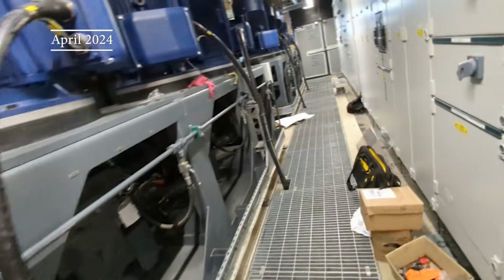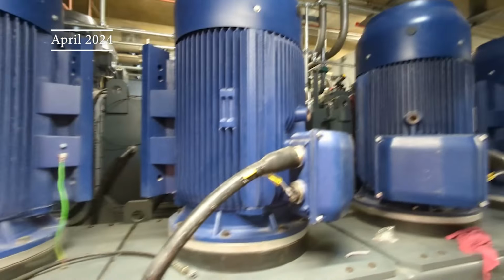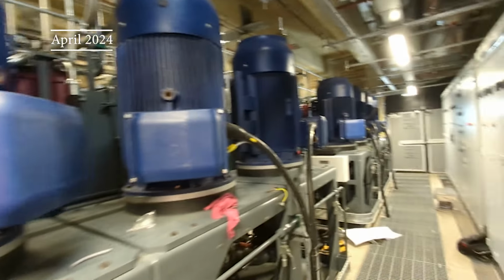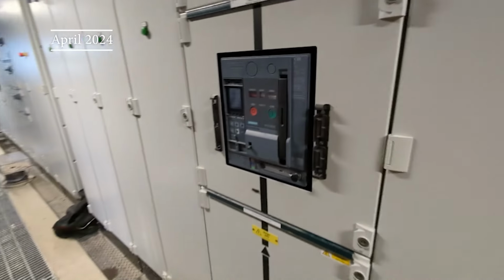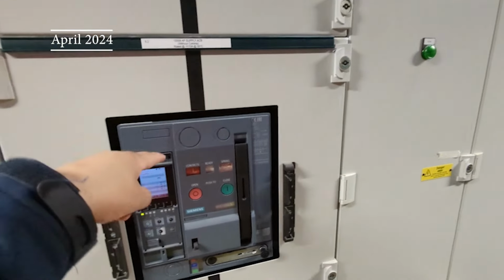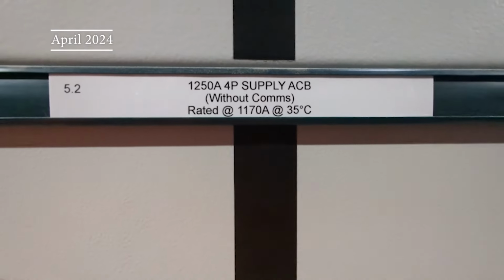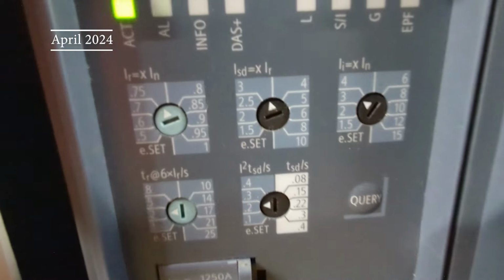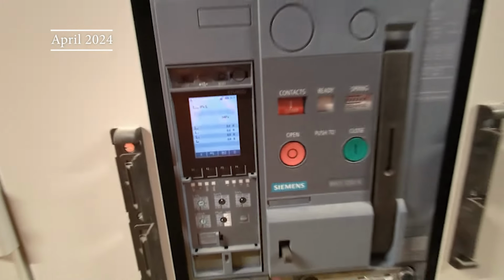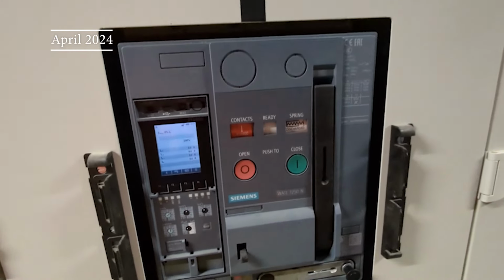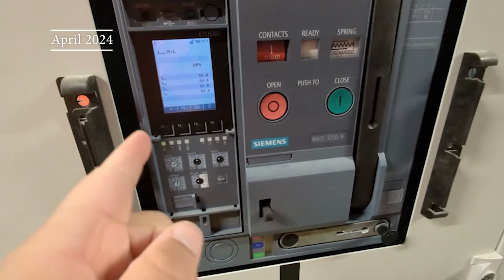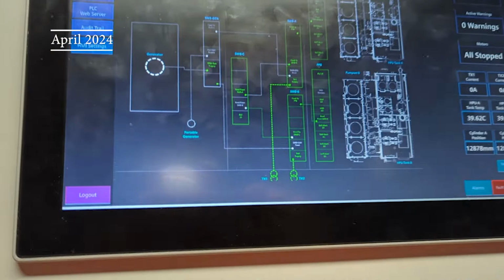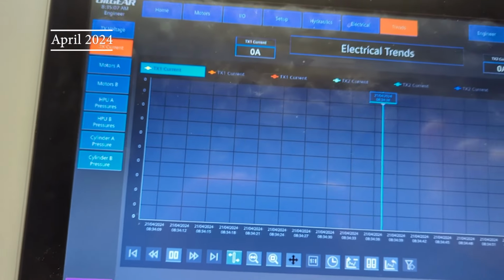Then if I take it next door to the hydraulics, these are the HPUs, the hydraulic motors and pumps that lift the bridge. So from inside the LV room into here, these get fed, feeding another 1250 amp circuit breaker. And again, this one should be blowing. That's down at 0.75, so it should be blowing at like 900 amps, and it's not. So I'm going to get a screwdriver and adjust these LSI settings. First, let me show you what happened yesterday.